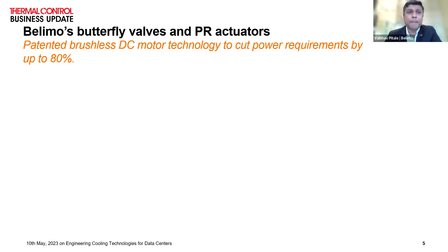I will probably come back to an energy valve, but there's also another important aspect in a butterfly valve when we talk about hydraulic cooling systems, which is reliability and low power. We all want to ensure our systems are more efficient and sustainable, and there has to be zero leakage, because if there is a leakage, you need to pump in additional water throughout the system, which decreases the PUE or efficiency of the system.